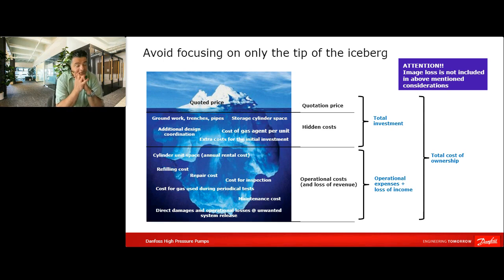And once it's finished and the system is commissioned and handed over to the operator, you will always have those regular gas distribution tests, and you need to empty the cylinders and then refill them again. You have to consider the regular maintenance costs. For sure, we also have maintenance procedures for a high pressure water mist system, but this, collected together with all those hidden costs in the installation phase and generation, makes the thing much more expensive.